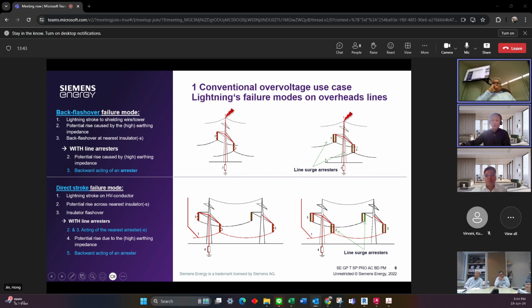So with such surge arrester protection, if you install enough surge arresters on the tower, for each or some of the insulators, you can reduce the tripping failure rate to a very low level or even to zero. We have a very good example from some countries, like South Korea. The state utility there is KEPCO, Korea Electric Power Corporation, and they have installed more than 200,000 pieces of EGLA on the transmission lines. Until today, they have benefited a lot, and they can reduce the tripping failure to close to zero, avoiding such flashover problems on the transmission line.